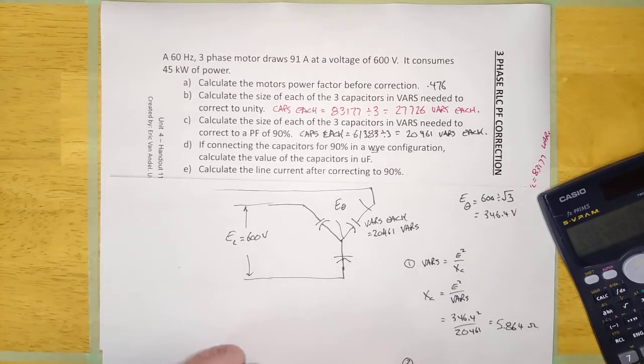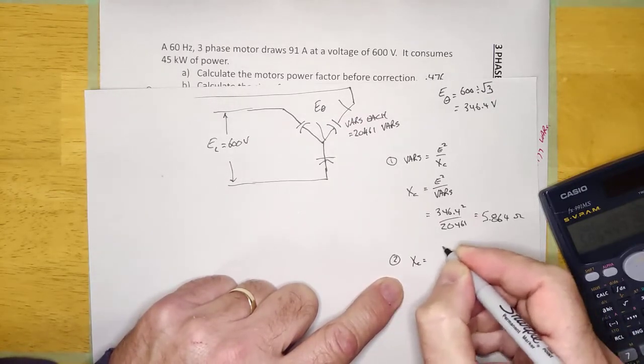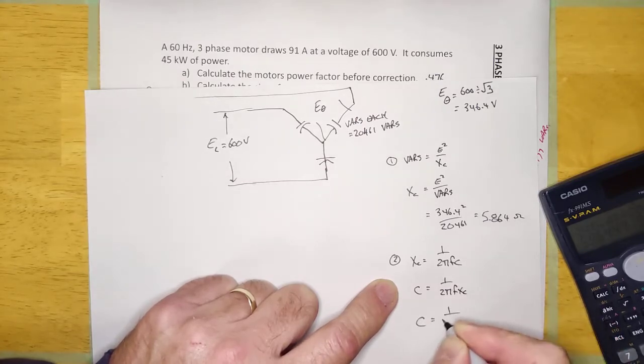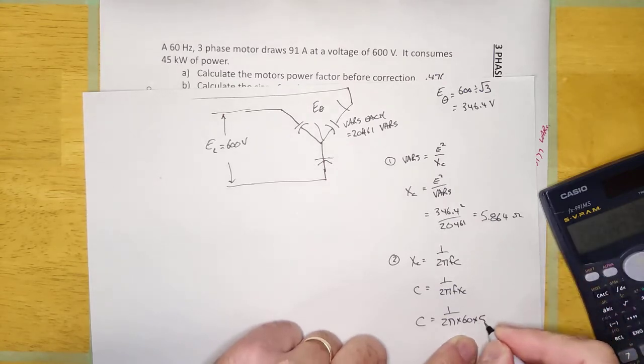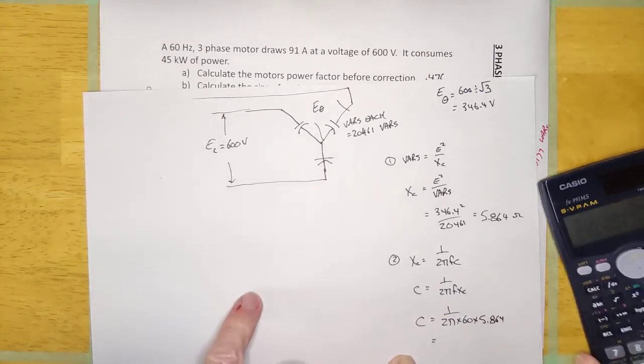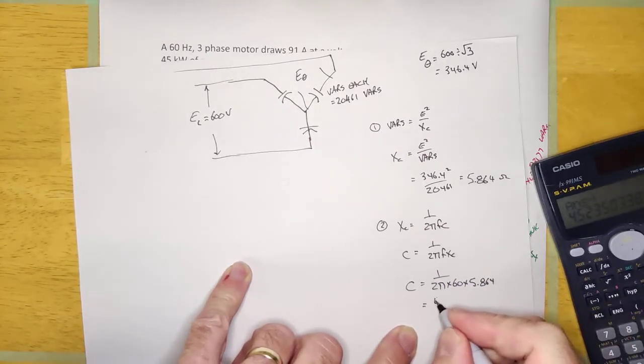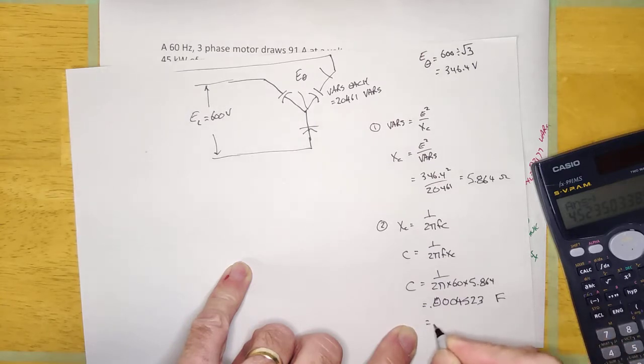And that's step one. And then step two, I don't want to go off the page here. So, C is going to be this formula right here. XC is equal to 1 over 2 pi FC. So, C is equal to 1 over 2 pi FXC. And so, C is equal to 1 over 2 times pi times 60 times 5.864. We'll go 2 times pi times 60 times 5.864 equals, and then hit 1 over X, then equals. And it's going to come to 0.0004523 farads, which is equal to 452.3 microfarads.